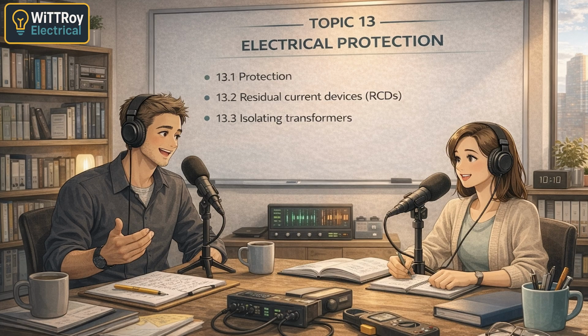Okay. Now let's talk about coordination. That's matching the device to the cable, right? Yes, the protective device must protect the cable it supplies. So the device rating can't be higher than the cable rating. Correct. If it is, the cable could overheat before the device trips. And if the device rating is too low, it trips too often. Exactly. That's nuisance tripping. So correct selection is important.